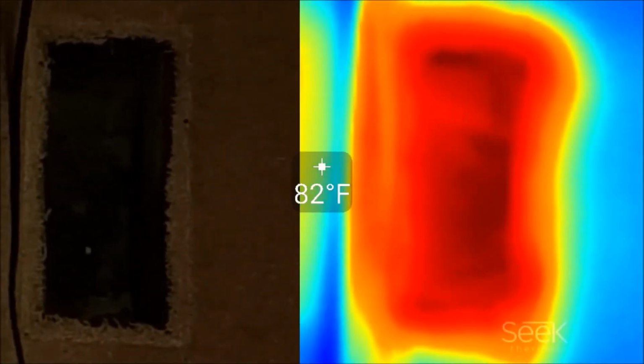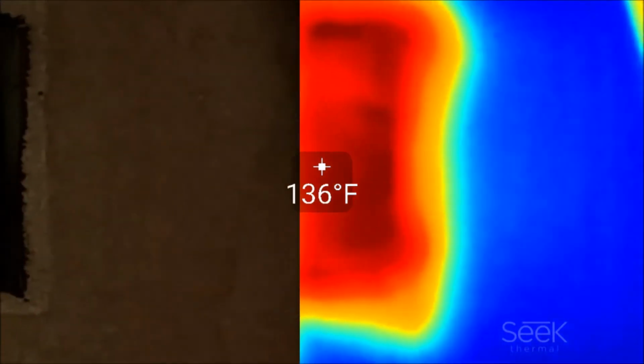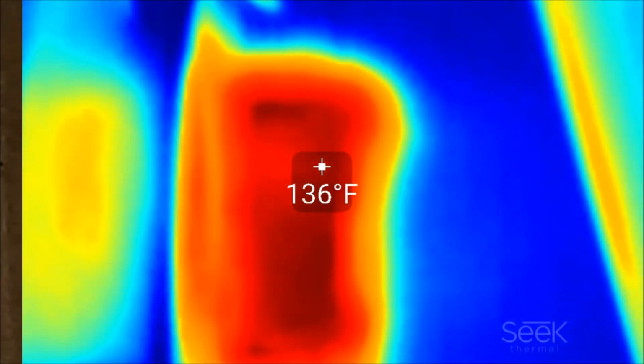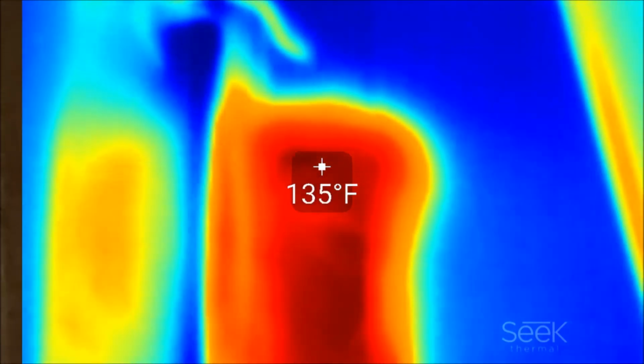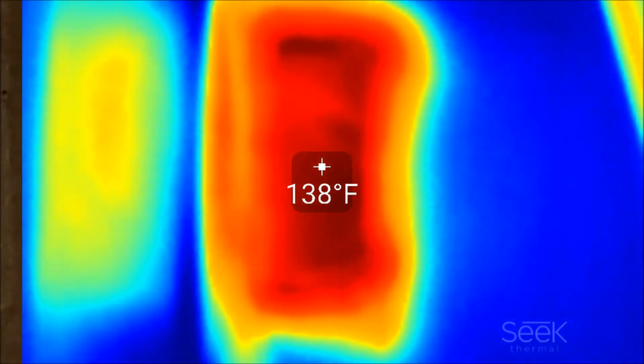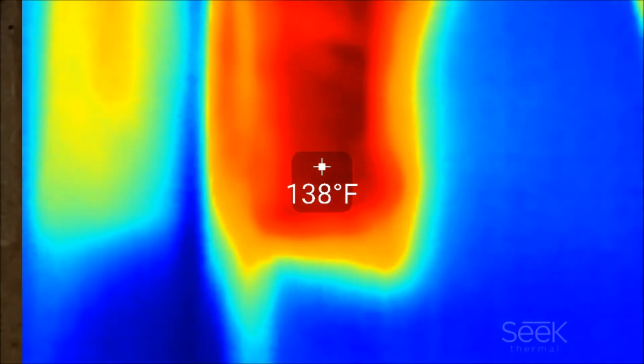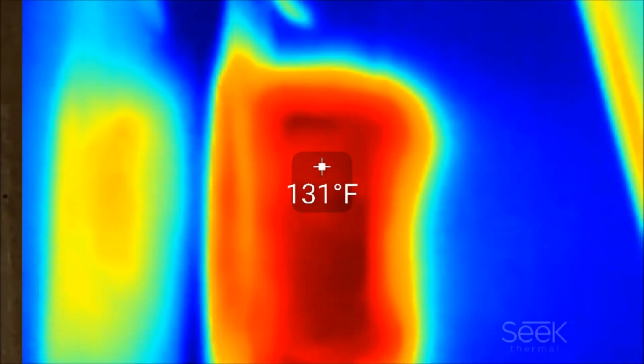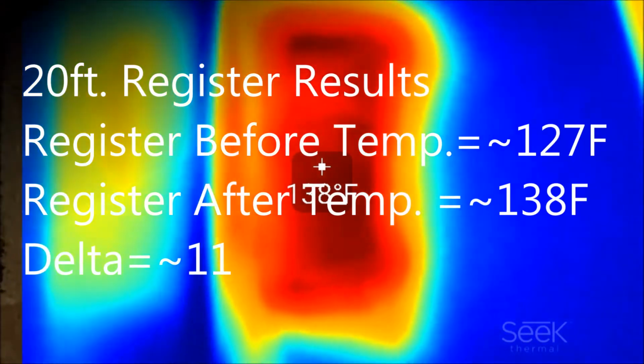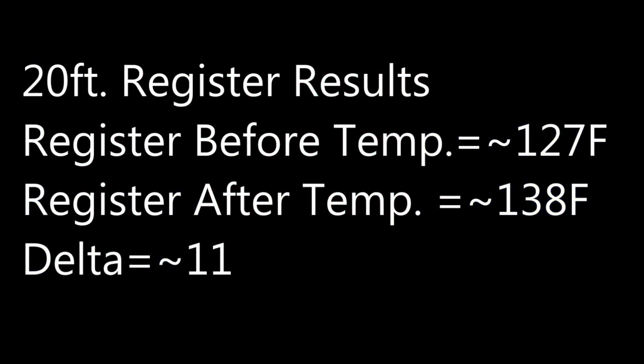So the next thermal image will be with the duct wrap on the 20-foot length, and you see a significant increase, not as much as the 10-foot section, but it does go up. So again, the 20-foot, 10-foot section, doesn't matter what you're doing, you're going to see an increase in temperatures. So this is my results after the test. You can see at 127 I started out, I ended up at 138, and that's an 11-degree increase.